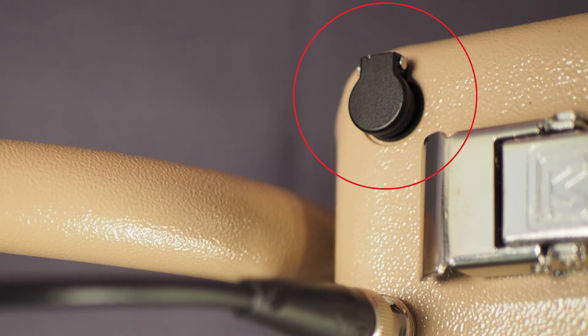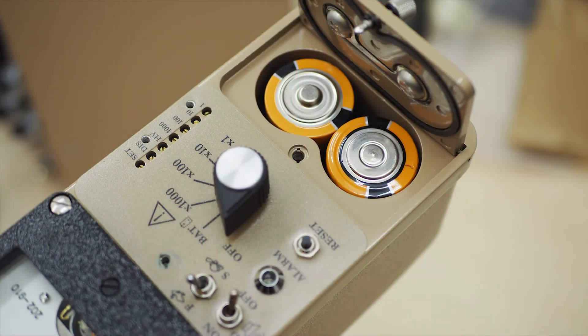A headphone jack is located near the detector connector. The battery compartment is located on the front of the meter. The model 193-6 uses two D-cell batteries. These can be regular or rechargeable batteries, although the instrument is not capable of recharging batteries.